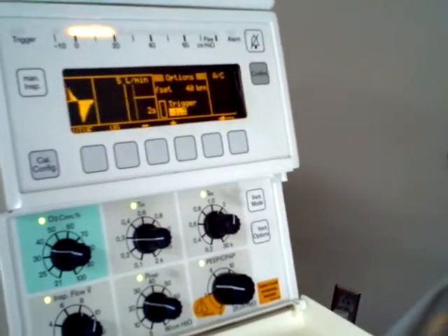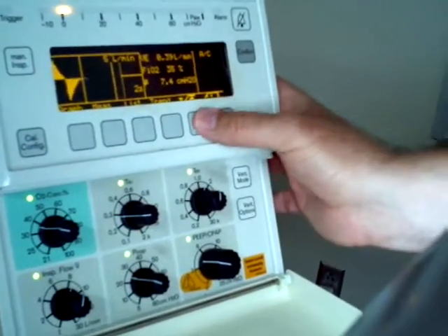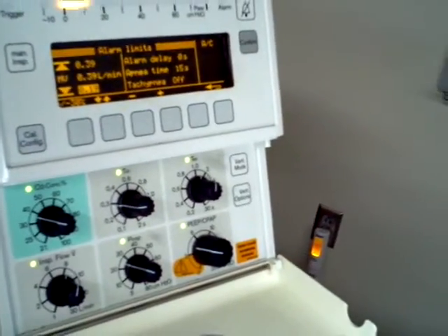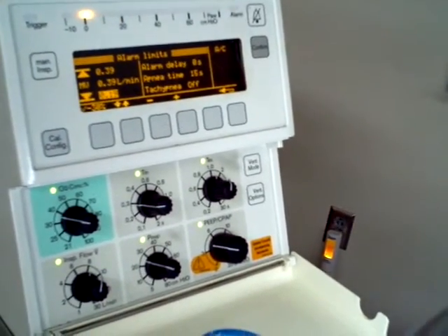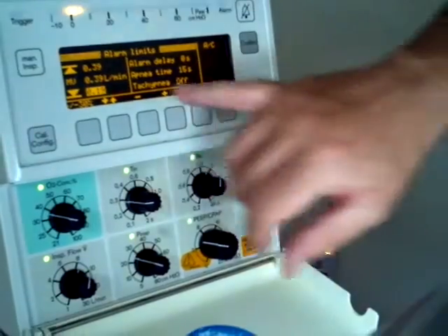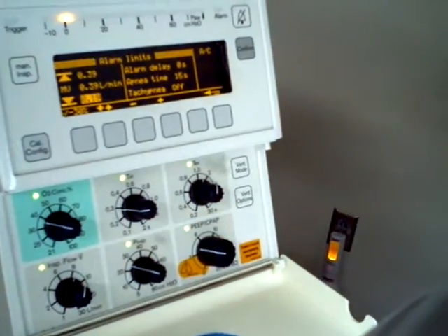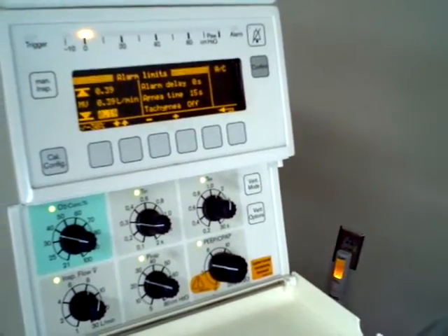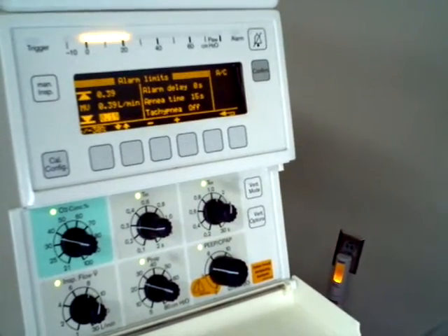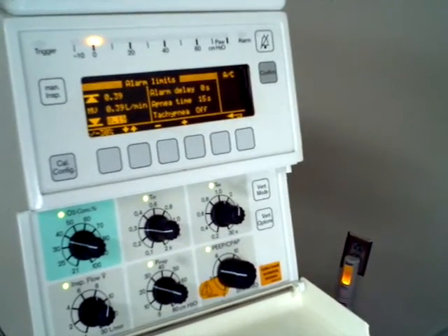Okay? Minute volume alarm. Yeah, let's do the alarms. That's what it takes to trigger alarm. Okay, so here's my alarm screen. These are pretty much all the alarms you can set on the Babylog. Our current minute volume is 0.39. We have an alarm that will go off if it goes above our high limit or below our low limit.